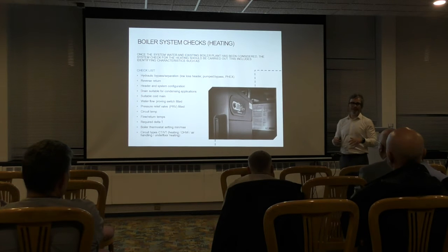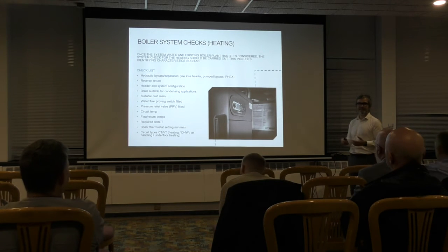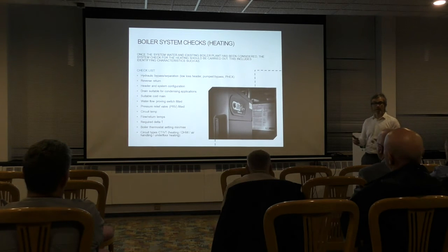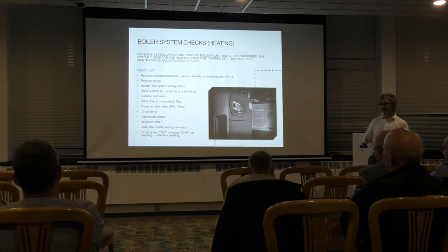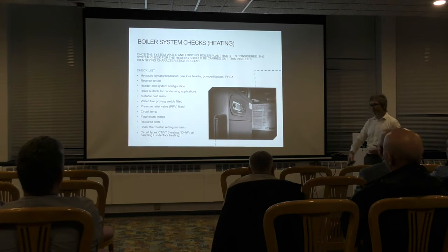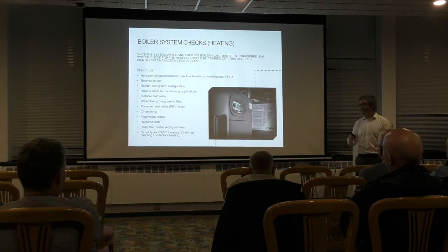But we don't want to start changing the flow and return temperatures in our system to say 70-40 or something, because then we know our boilers are going to condense. If you do that, then your heat emitters on the other side aren't going to work because they're all sized on 11 degree delta T and that higher flow temperature. So what I would say is keep your secondary side on 82, 71, but then maybe put your condensing boilers in there, maybe a low loss header, keep the primary side on a 20 degree delta T, secondary side on 11. You could put the condensing boilers in because we've got certain condensing boilers that are okay on an 11 degree delta T. They can work, it's not a problem.